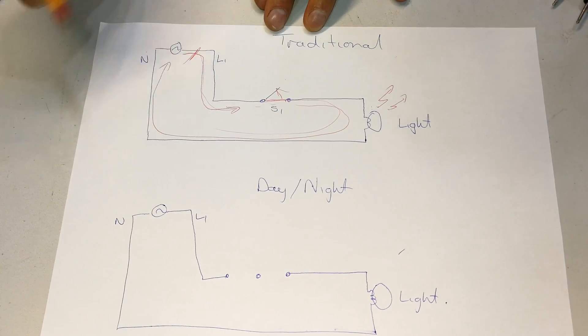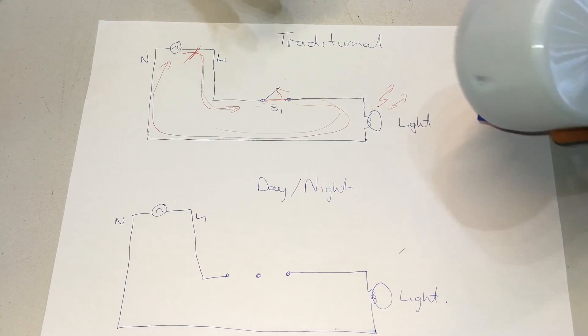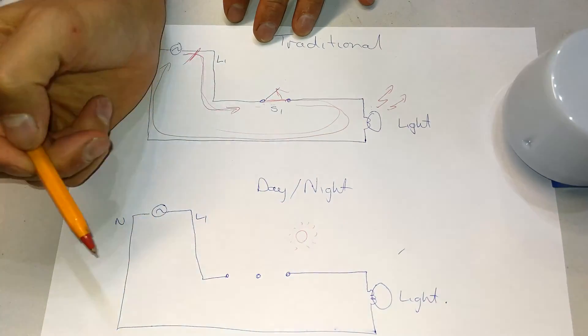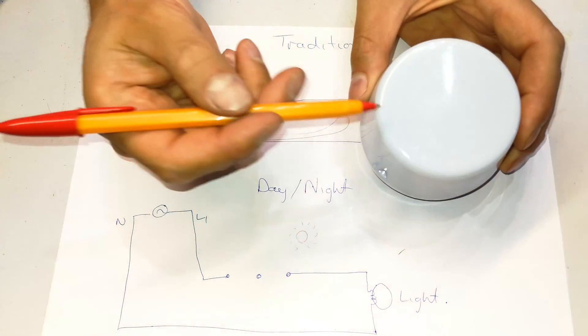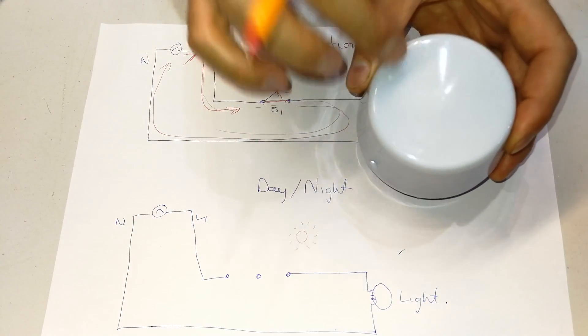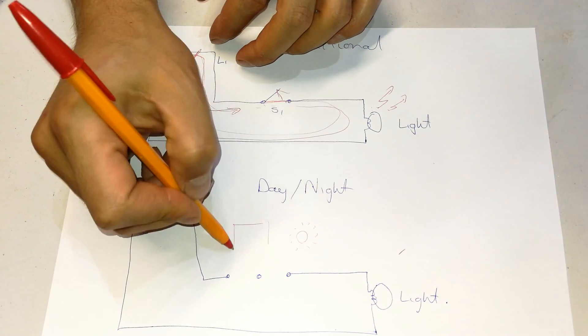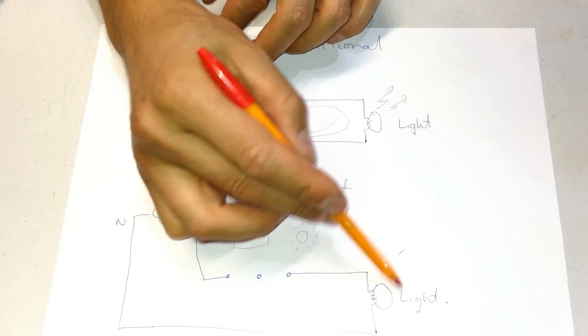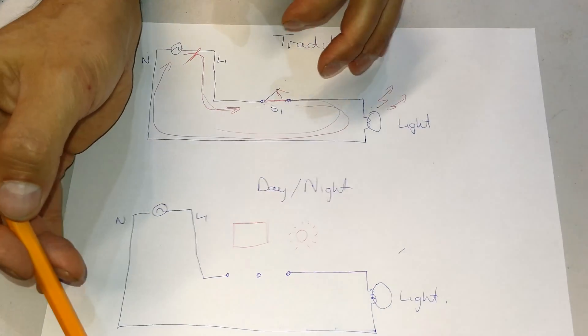So what does the day-night switch do? Well, this is automatic. It means that based on the sunlight—or if there's a lamp shining on it, because that sometimes does happen—that's one of the reasons why the placement of this is very important. Because if you install a floodlight and the floodlight shines onto the day-night switch, well then you got a problem. So what you want to do is install your day-night switch somewhere out of the direct radiation of this light. You'll put it kind of maybe under a part where this light doesn't shine on.